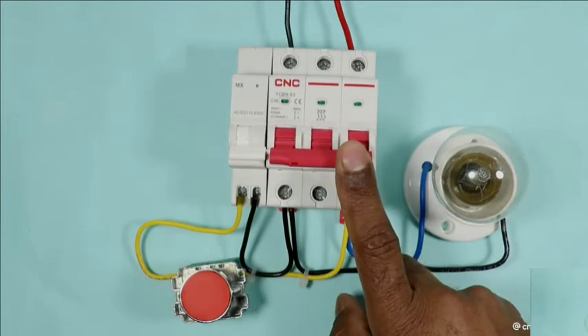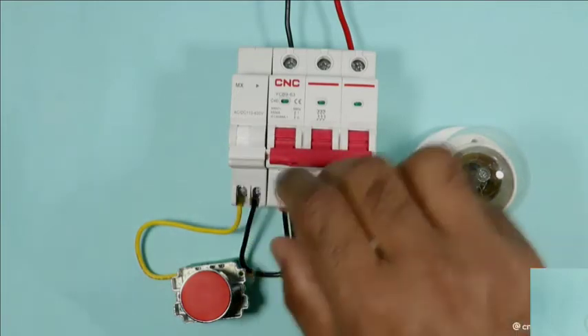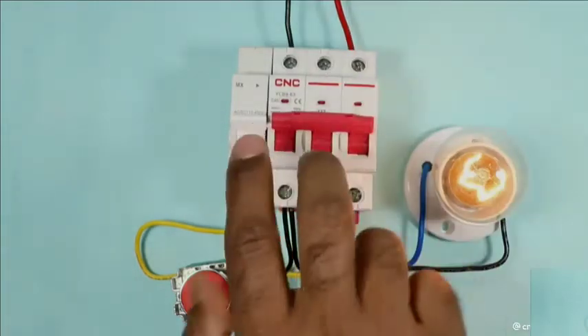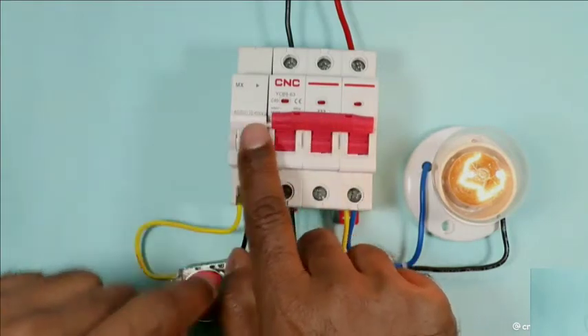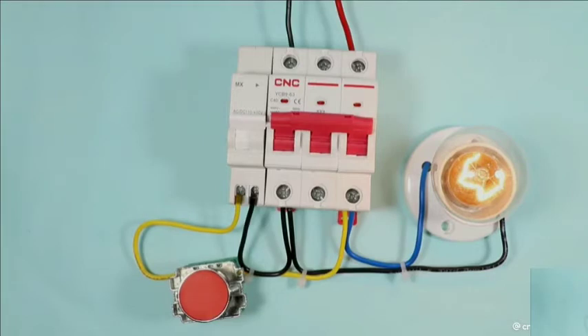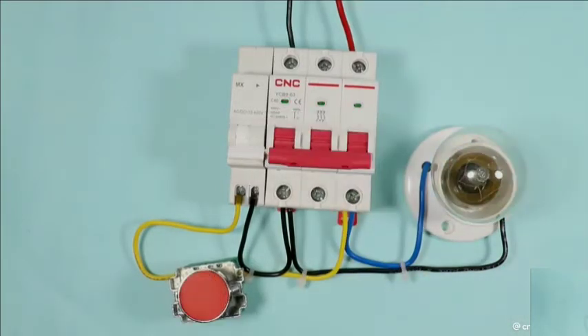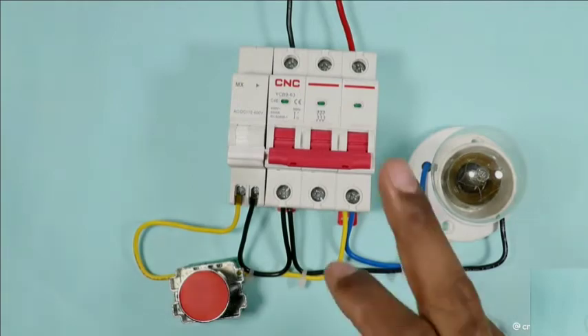Now if I turn on the MCB, you will see this shunt coil also turns on. You can see both turn on together. This is happening because we interlock both of them together. If I press this push button, our MCB will turn off. I am pressing this. You saw that on pressing push button, MCB turned off.